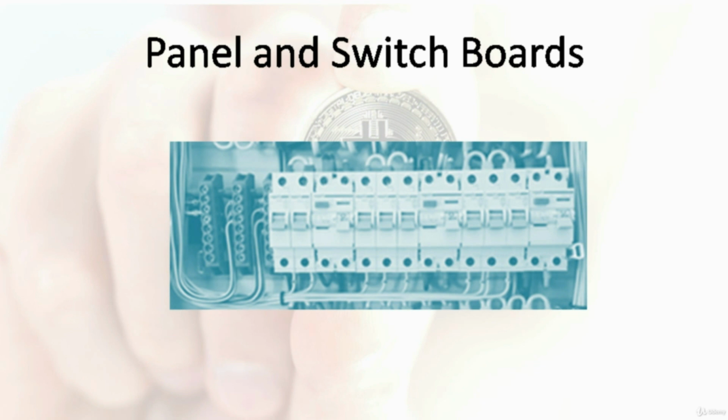Switchboards, on the other hand, are devices that direct electricity to many smaller regions of use from one or more sources of supply. A switchboard is an assembly of one or more panels, each containing switches that allow for the redirection of electricity. Its function is to allow for further diffusion of the current supplied to the switchboard into smaller currents, and to provide switching, current safety, and possibly metering for these different currents. Switchboards will typically distribute power to transformers, panel boards, control equipment, and to individual system loads.